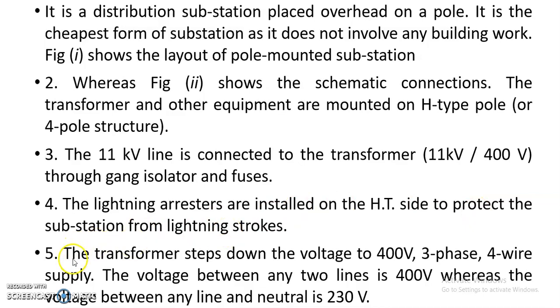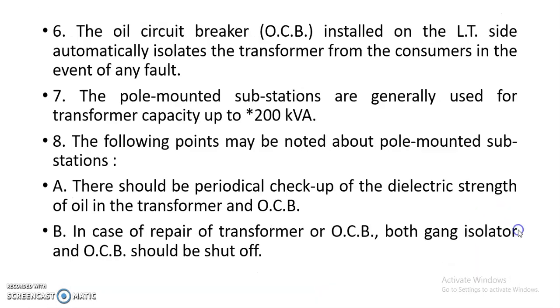Then the transformer steps down the voltage to 400 volt, 3 phase 4 wire, and the voltage between any two lines or any two phases is 400 volt, whereas the voltage between any line and neutral is 230 volt. That means if we require a 3 phase supply, we can directly take the 400 volt 3 phase supply from this pole mounted substation, and if we require a single phase supply, we take any one phase and neutral. So we get a 230 volt single phase supply.